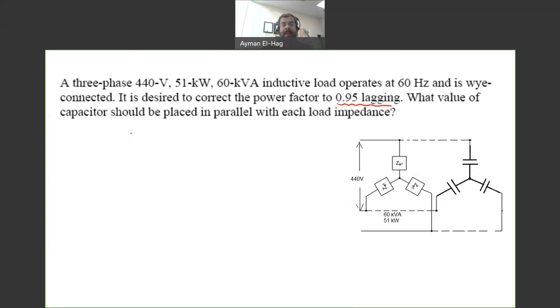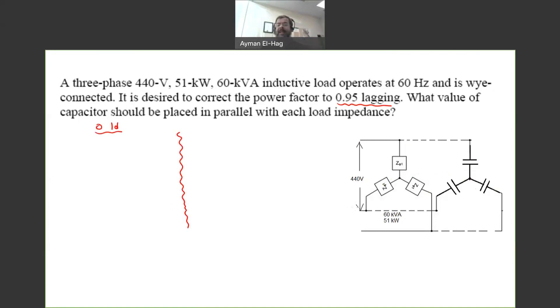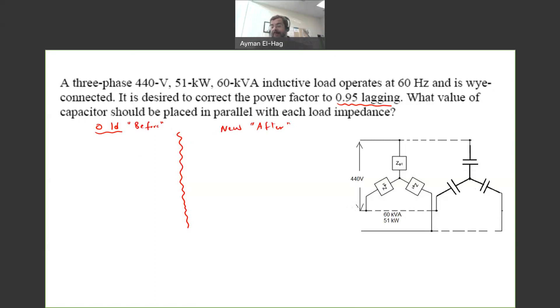The approach here uses two parallel calculations. I will call this 'old,' referring to the data we have before we connect the capacitor bank — so this is 'before.' Then I will have 'new,' which is after. In each case we have three quantities to identify: P, theta, and Q.